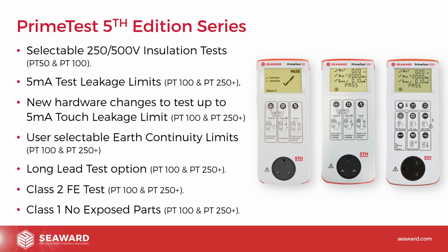We mentioned Class 2 FE, Class 2 Functional Earth. We've actually added that functionality onto the Class 2 test, again for the Prime Test 100 and the Prime Test 250 Plus. So if you are testing Class 2 FE equipment, when you do a Class 2 test, if it detects an earth path, so if it detects an earth connection, it will actually ask you, is it Class 2 FE? And if it is, you can carry on and do that continuity test as well as the Class 2 insulation resistance test and the leakage test, and that will give you the values for doing that. So you can actually carry out testing of Class 2 FE equipment. Again, that's another 5th edition requirement.